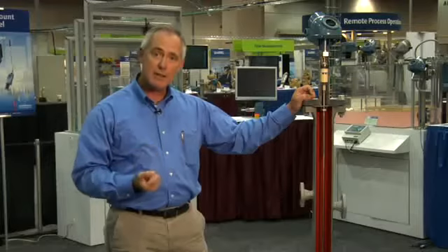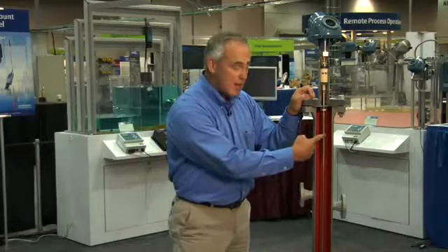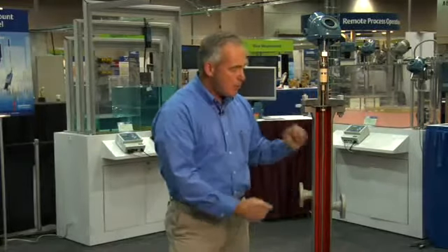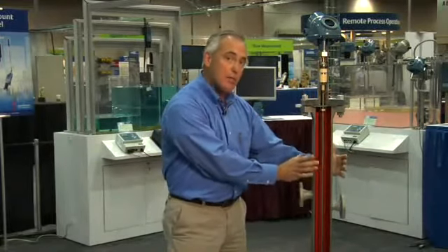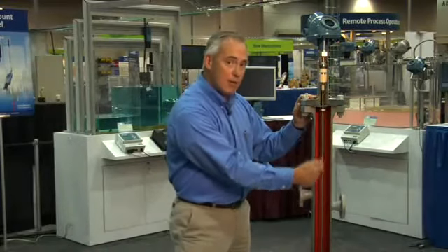The third feature I'd like to point out on the 5300 is its probe design. As we mentioned earlier, there is a tendency for a product called magnetite to build up in these types of measurement applications. And you don't want a device that's going to allow that material to build up and interfere with the measurement. So we've designed this device with a single lead probe, and we put that single lead probe in a large diameter bridle. So all kinds of product could be in this space here and it will not interfere with the measurement. We can't say it's immune to buildup, but it's very resistant to product buildup.